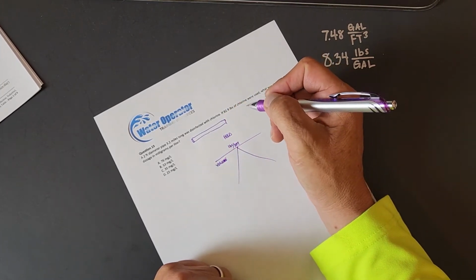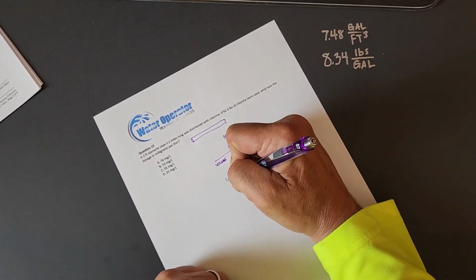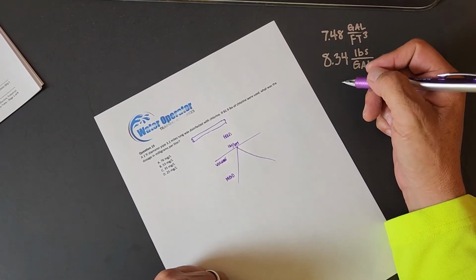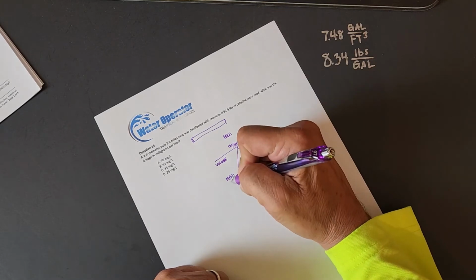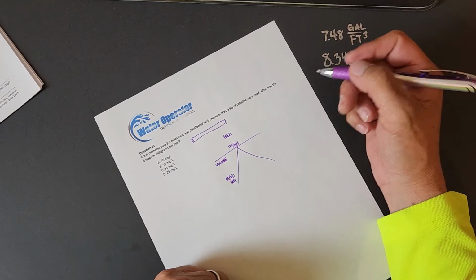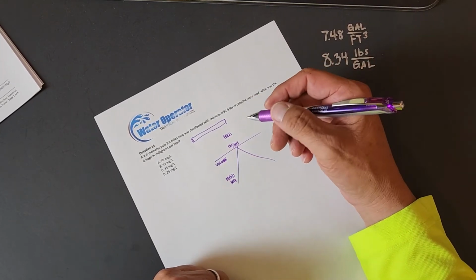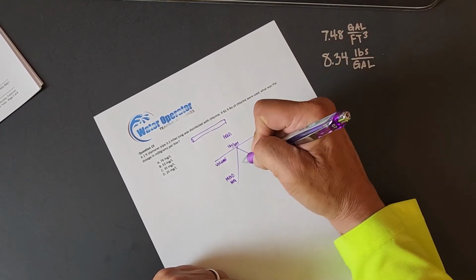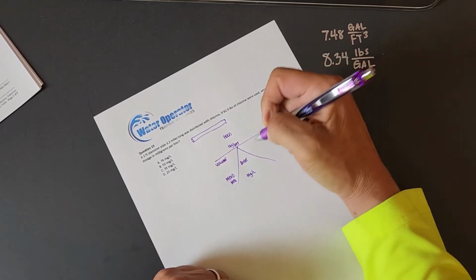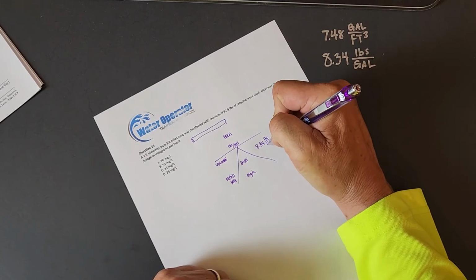But instead of volume in cubic feet or in gallons, I'm going to use the unit of measure million gallons per day. We could even say million gallons, because we're talking about a volume, not a time period. We want dose in milligrams per liter. The weight of water, 8.34 pounds per gallon.